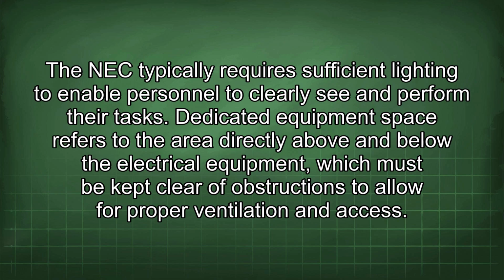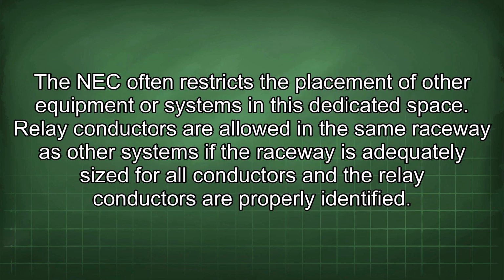Dedicated equipment space refers to the area directly above and below the electrical equipment, which must be kept clear of obstructions to allow for proper ventilation and access. The NEC often restricts the placement of other equipment or systems in this dedicated space. Relay conductors are allowed in the same raceway as other systems if the raceway is adequately sized for all conductors and the relay conductors are properly identified.